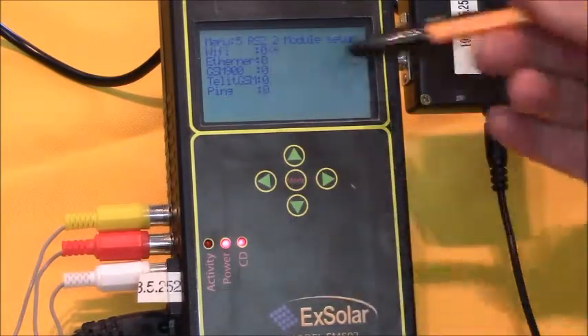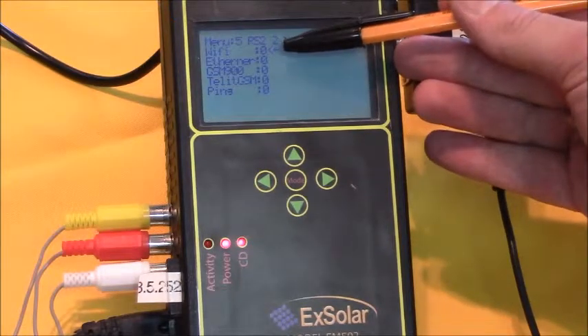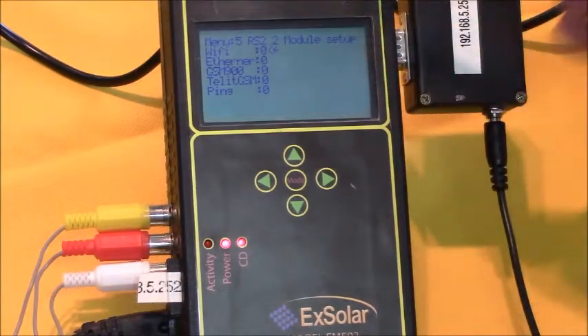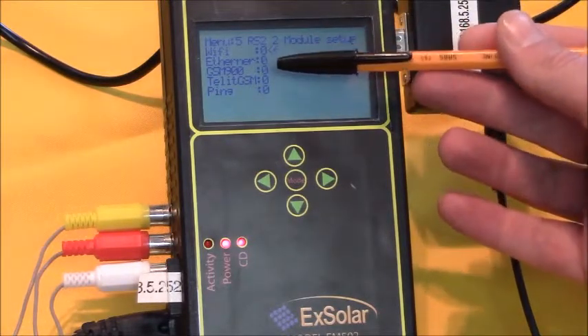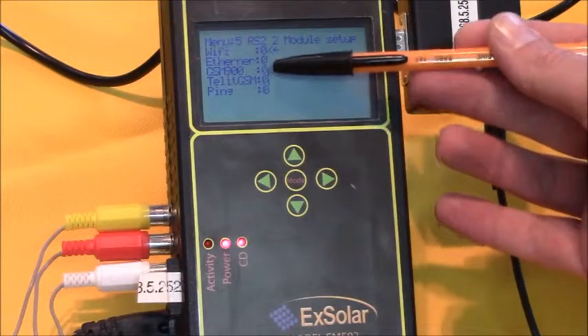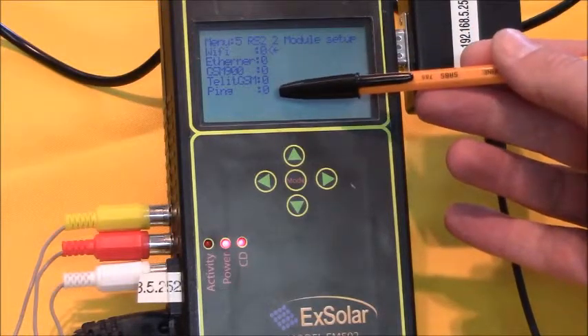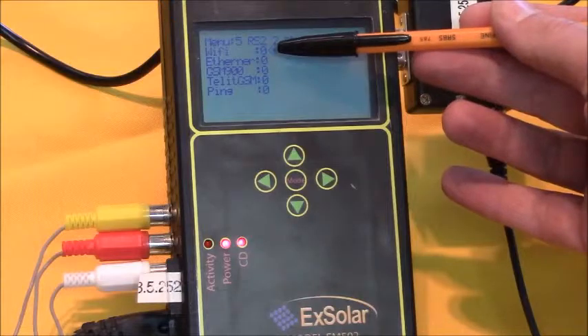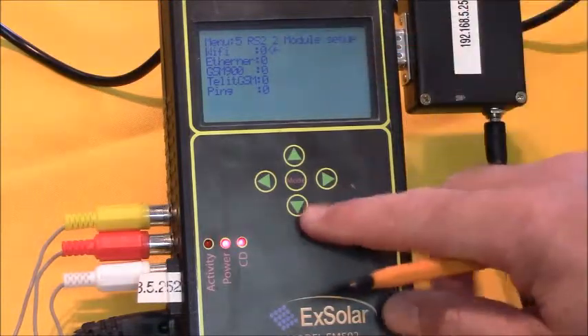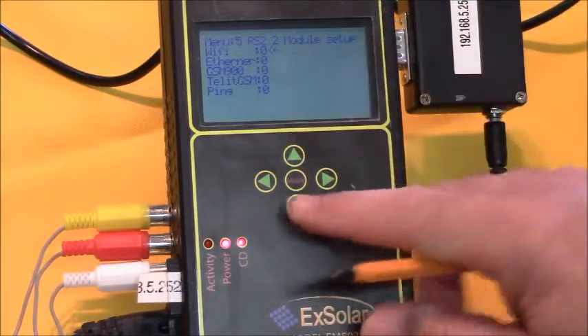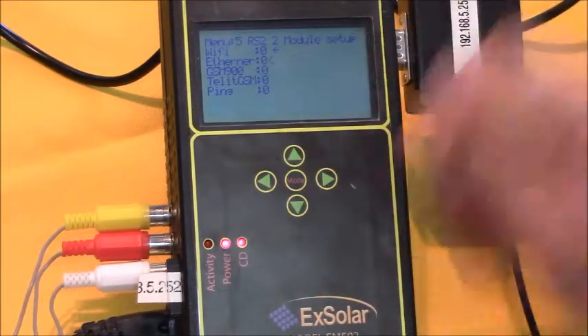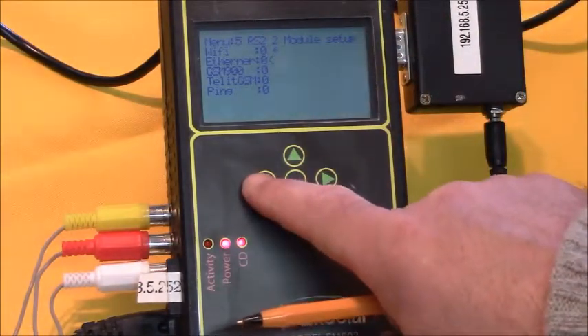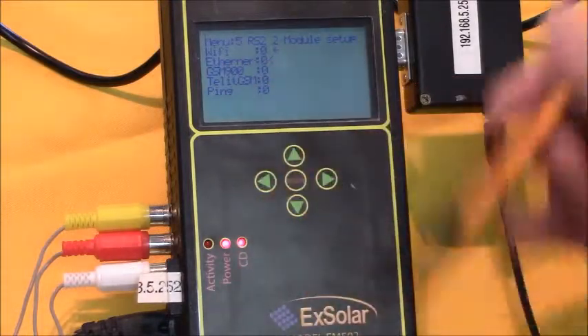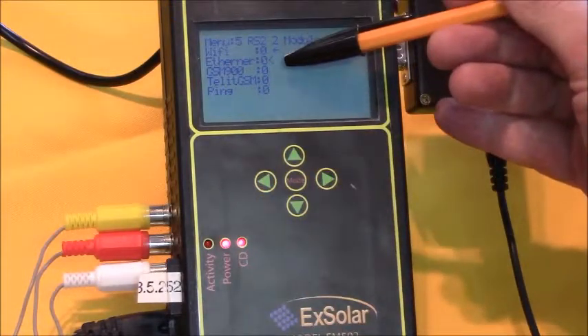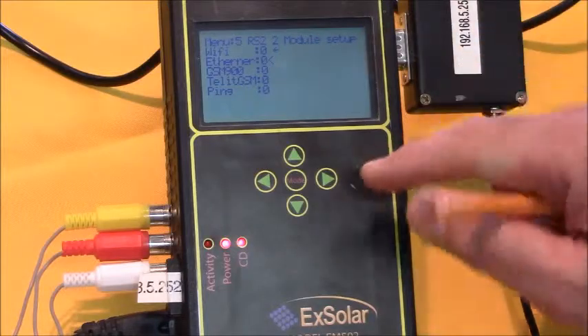And the last screen shows there's an arrow beside Wi-Fi, which means that this particular unit has been set up for the Wi-Fi. We've also got the Ethernet and the GSM. There's two different GSM modules which we use, and then there's a ping function as well. To activate the Wi-Fi, if we were changing from Wi-Fi to Ethernet, you would move the arrow down to Ethernet, push the left arrow key, and then it would activate that, and that arrow would move down to that location. I'm not going to do it in this particular case.